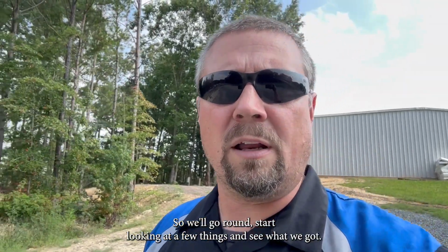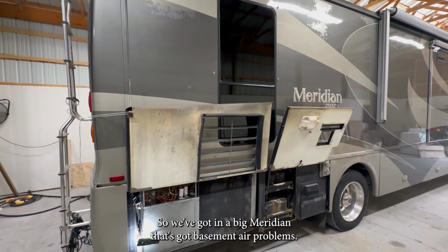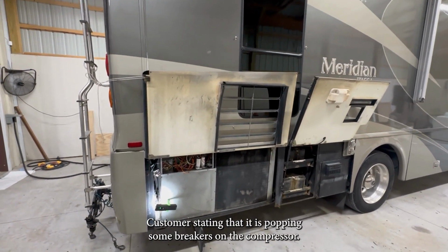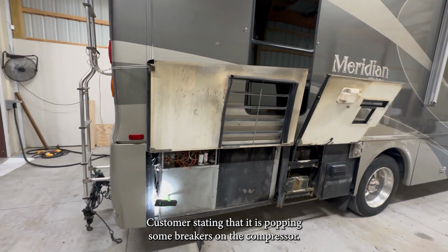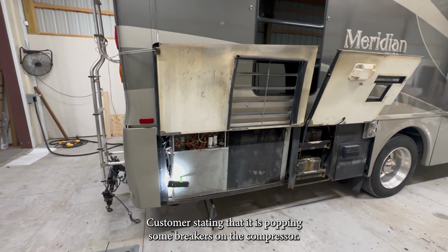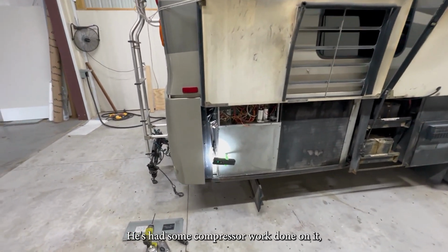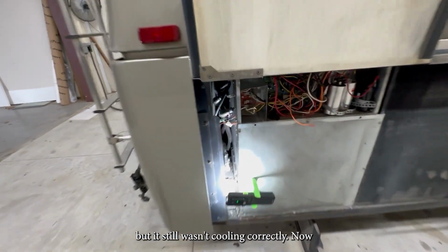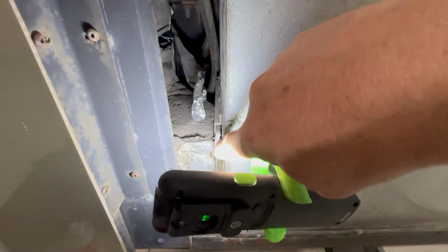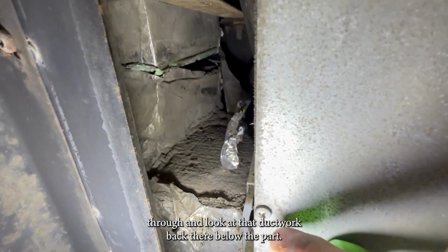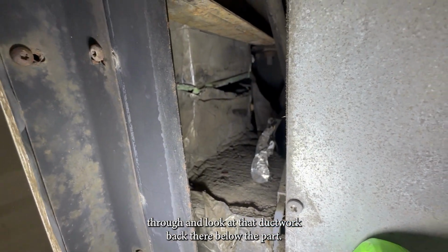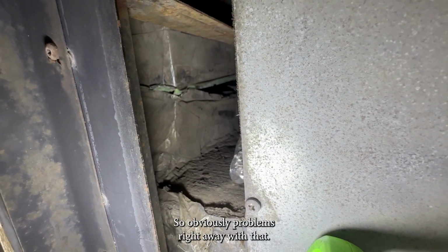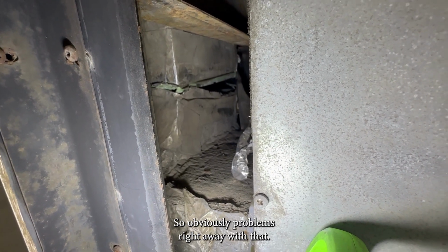So we'll go around and start looking at a few things and see what we got. We've got a big Meridian in with basement air problems. Customer states it's popping some breakers on the compressor. He's had some compressor work done on it, but it still wasn't cooling correctly. Now that's air bleeding through, and look at that ductwork back there, blown apart. So obviously problems right away with that.